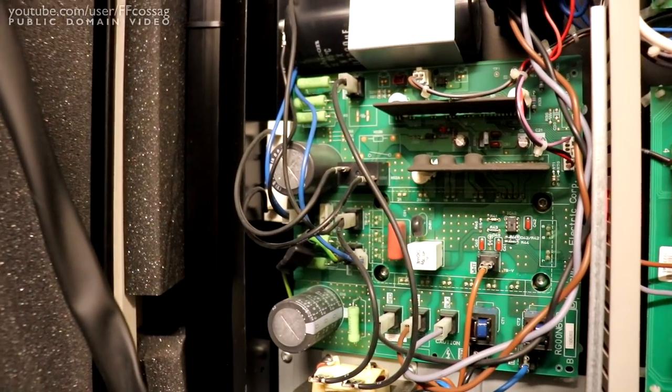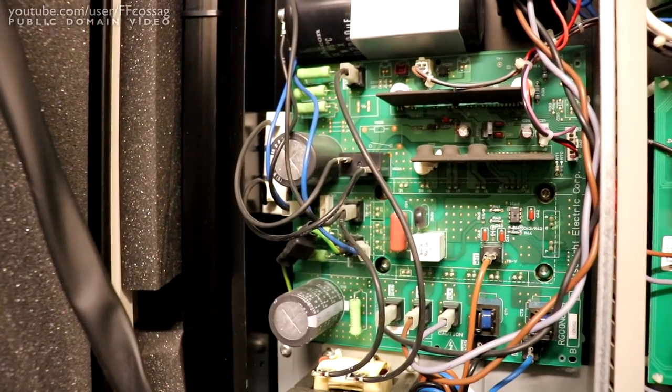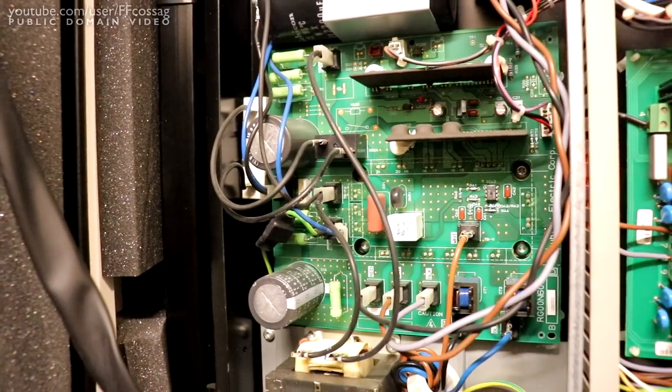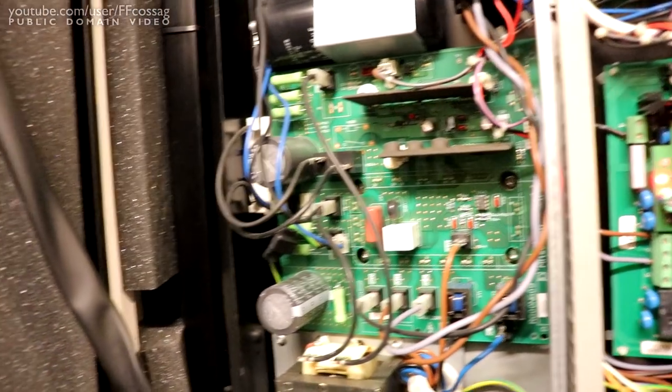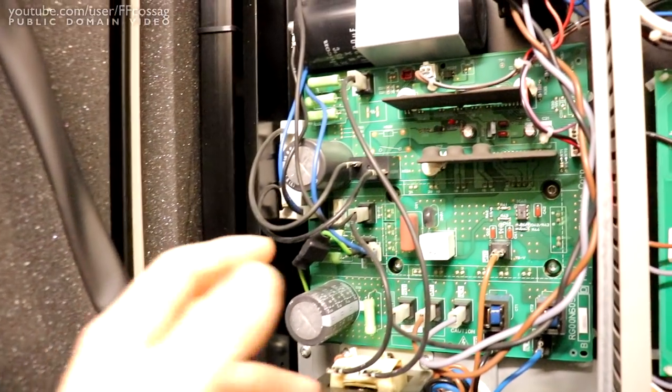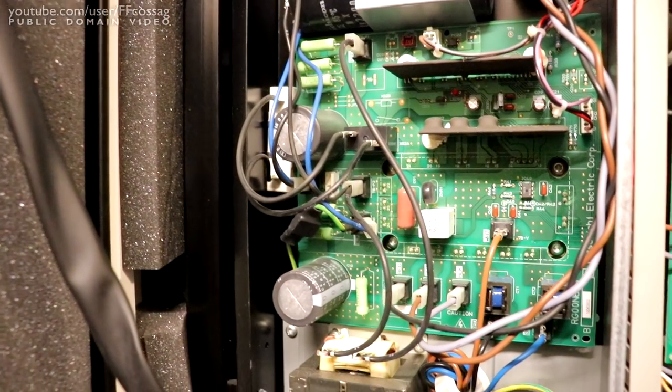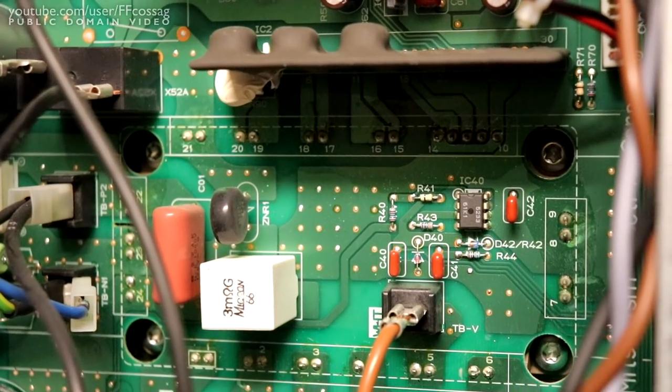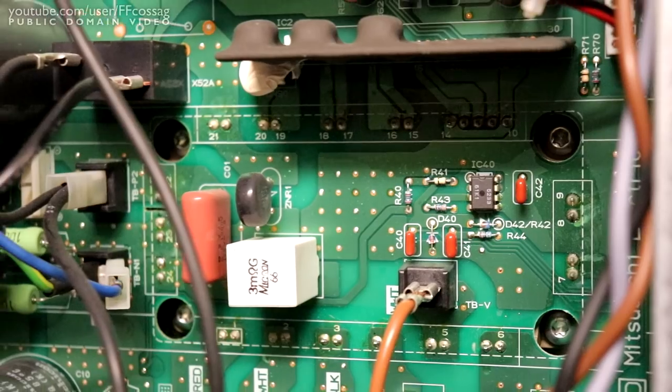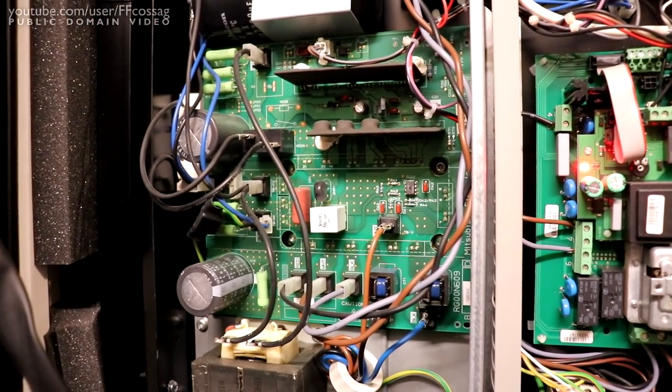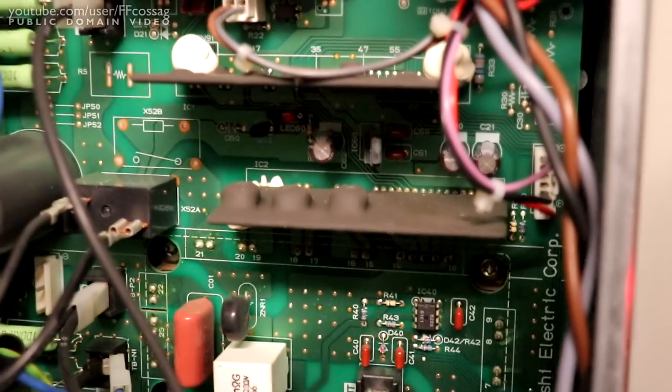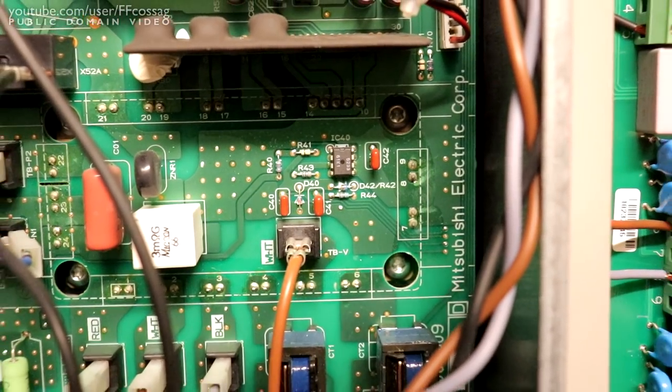And in the middle of the night about five in the morning when I got up and checked this, this resistor seemed to my tired mind to be open circuit so we're going to have to verify that before we dig any further. And naturally I really hope it's just that resistor and nothing further wrong like a relay failure that's caused further damage to the inverter board because this has one of those giant brick type STK devices underneath there so this board is basically unrepairable if it's failed and new ones if available is going to be hundreds and hundreds if not a thousand euros for all this horrible garbage. I think this is, yeah it's Mitsubishi so at least it's not internally engineered, it's going to be generic for this particular compressor model.